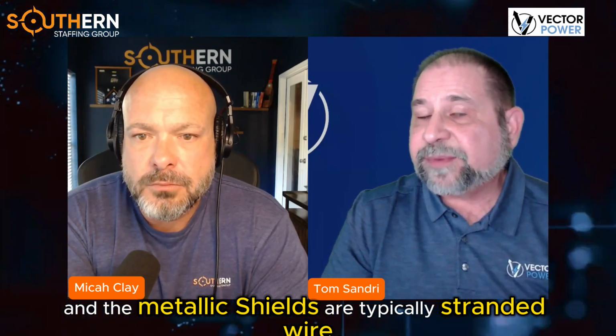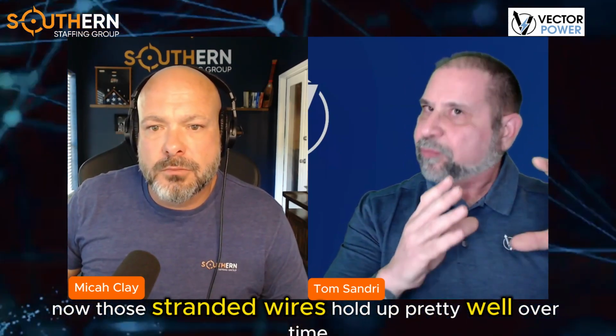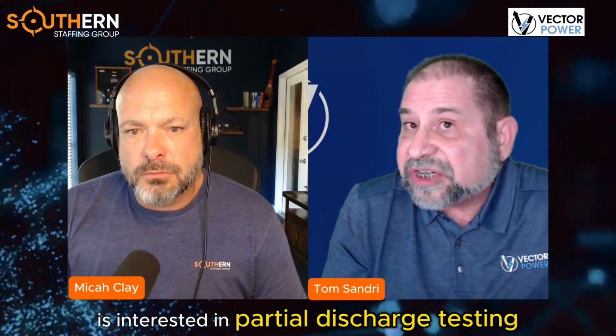We've been focusing on renewables, which tend to fall under the jurisdiction of the utilities. Utilities typically use cross-linked polyethylene or tree-retardant TRXLPE cables, and the metallic shields are typically stranded wire concentric neutrals. Those stranded wires hold up pretty well over time — they form good conductors with relatively low losses. So being able to see these very low-level signals through long distances isn't that difficult to accomplish in those environments. But there's a whole other industry sector out there that's interested in partial discharge testing.